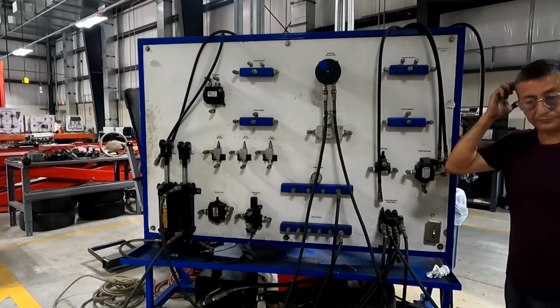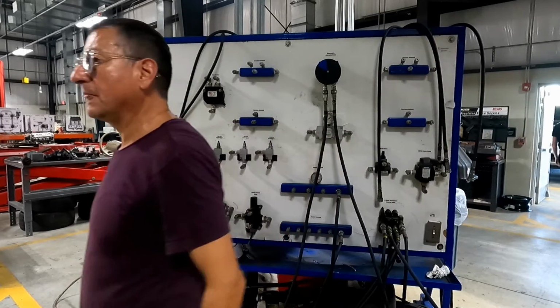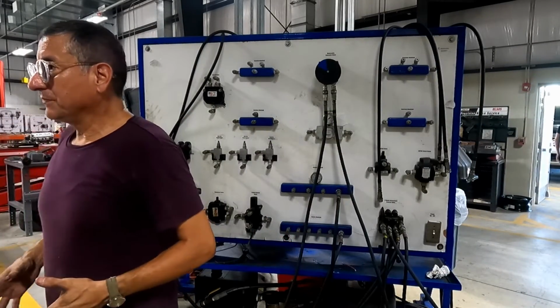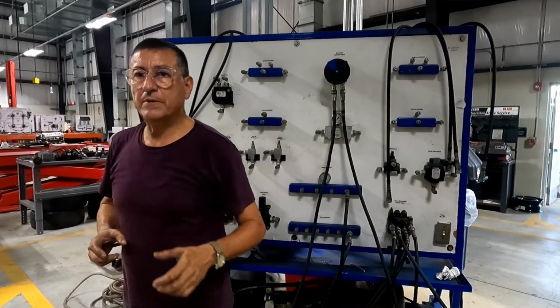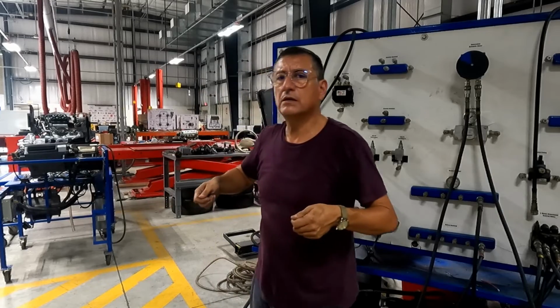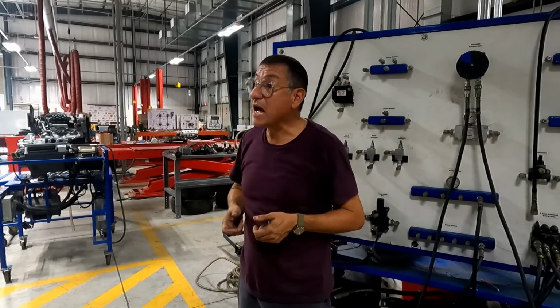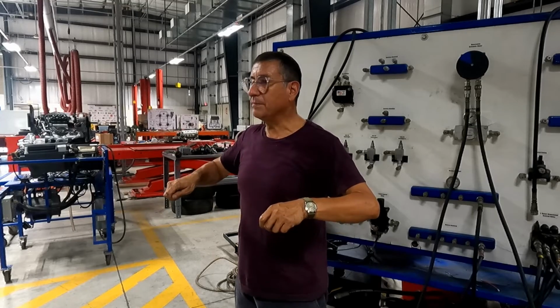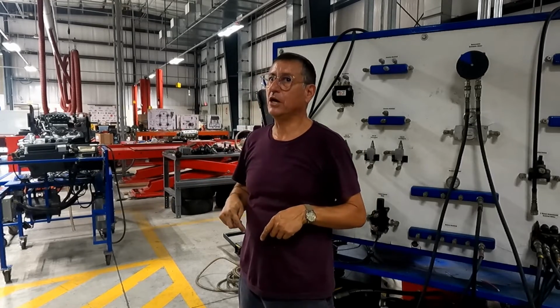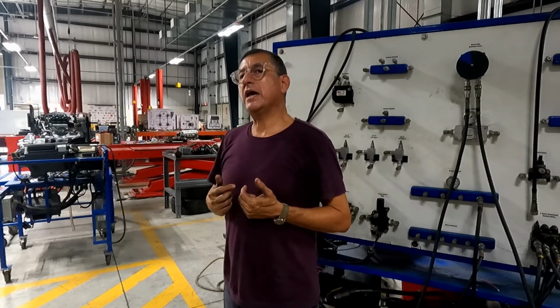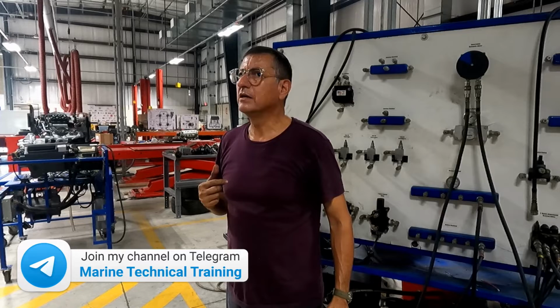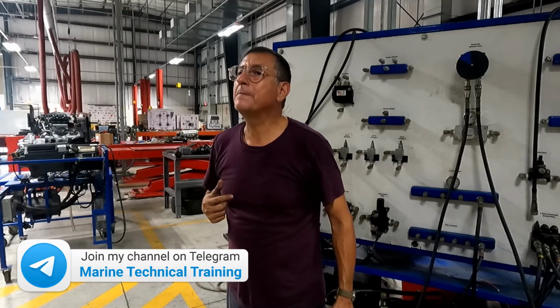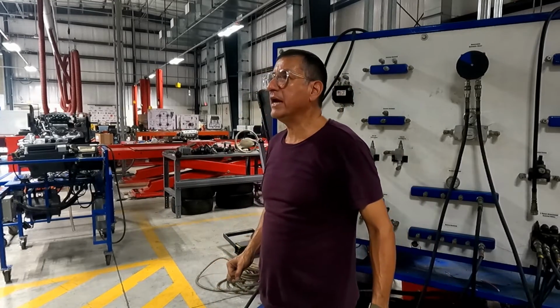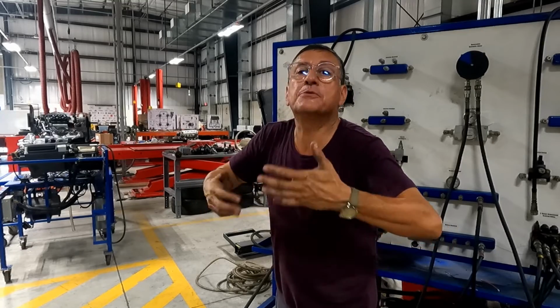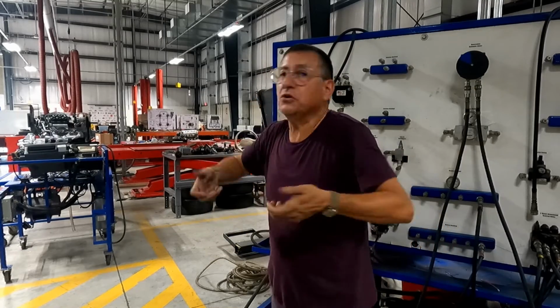Okay, guys, look at this. You remember in electrical panels when we connect the voltmeter and the ammeter? How do you connect the voltmeter? In parallel. And how do you connect the ammeter? You separate the cable and you insert it in series. I want to connect my voltmeter here. What is the voltmeter in hydraulic? Pressure. And the flow meter, flow in gallons per minute, like amps per hour. Flow is the ammeter, and pressure is the voltmeter.